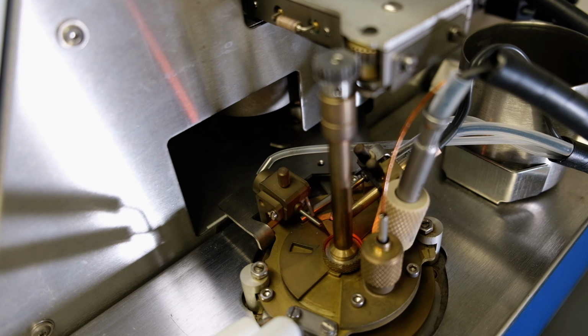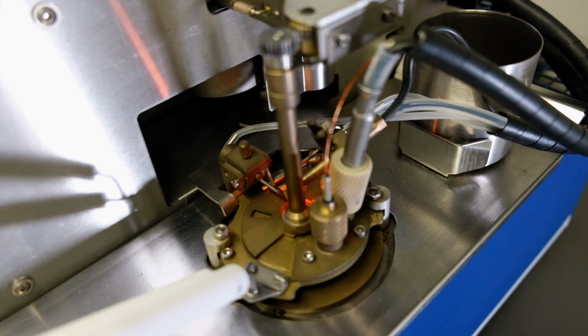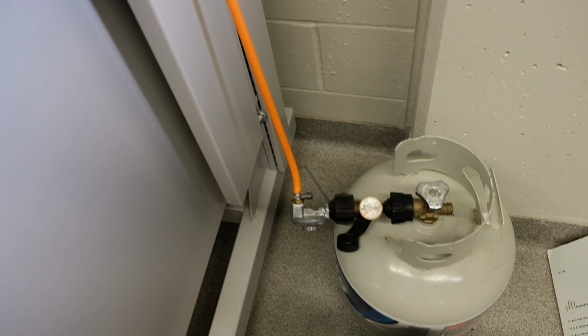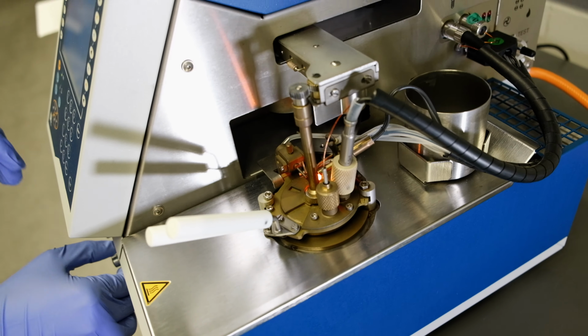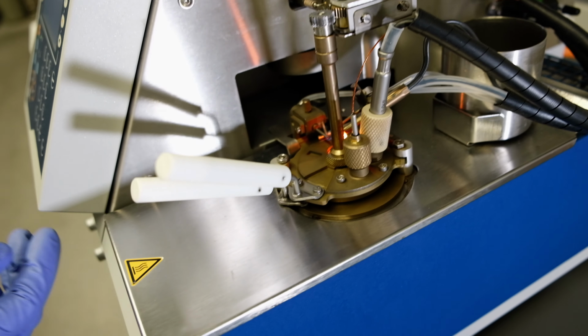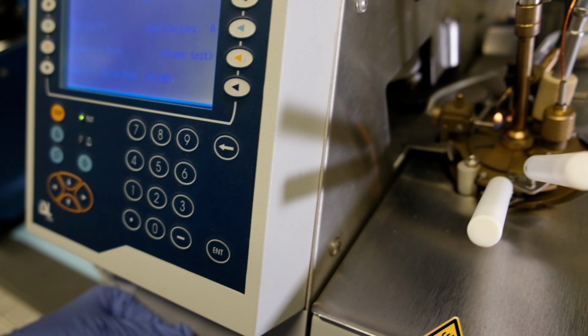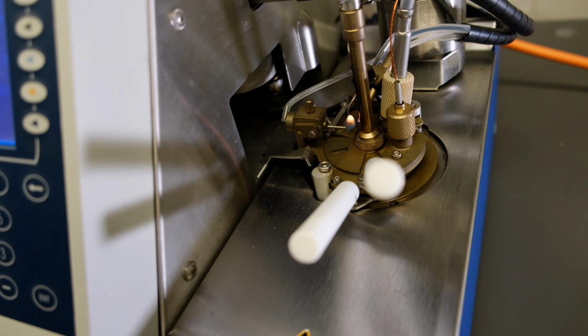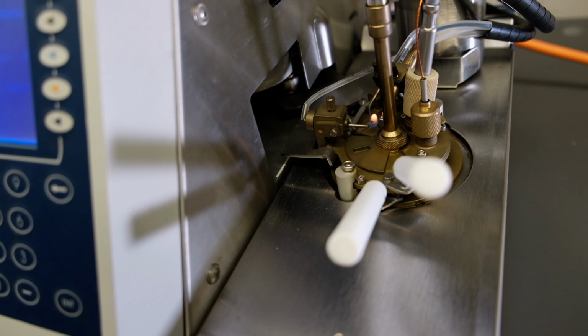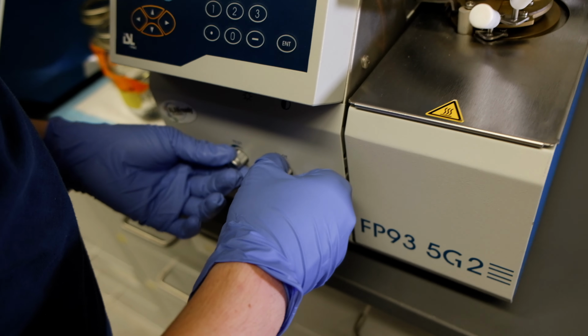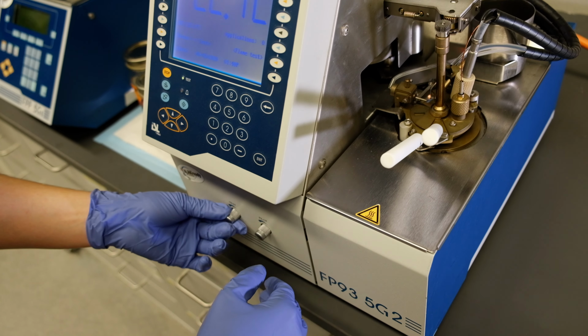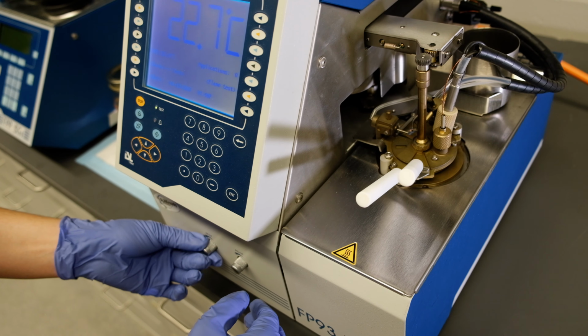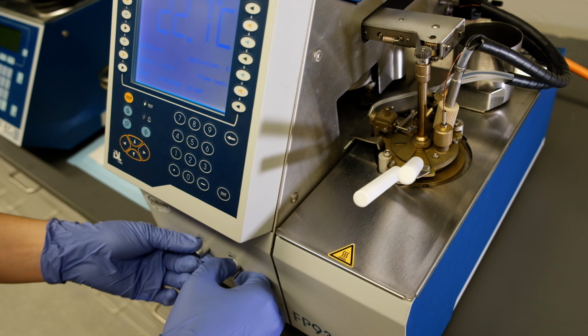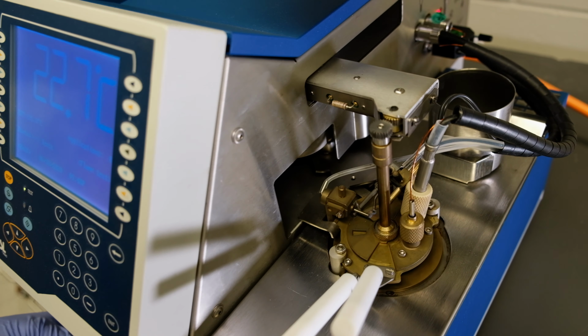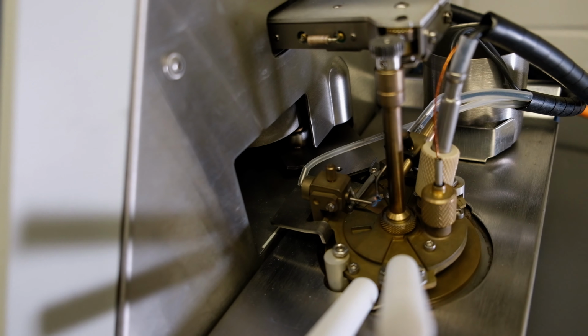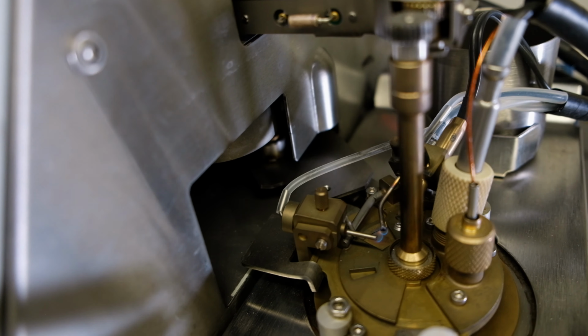And the point of that is that it's going to ignite your gas. And so you've got the test light and you've got the pilot light. That little curved one back there is the pilot light. And that's what you will use to ignite the flame that will be put into the fuel. The pilot light is supposed to be about the size of your pinky nail. And the test light is going to be just large enough where you have a little bit of orange flame on top. And so you can see there I've got two separate flames, one entirely blue and one little flame with a bit of orange on top.